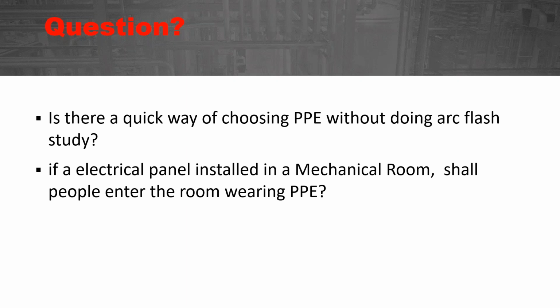Okay, thanks, Jay. Do you have any comments, Charlie? Yeah, absolutely, along those same lines. Here I want to promote Grace and what they call their safe test point, their voltage test station. I think this is a wonderful device, and I don't know if you see it in the background here, where I've got this device installed. The safe test point can go on industrial control panels. This would be a great reason to install one on older equipment, where company policy says it has to be de-energized. The safe test point connects to the incoming line voltage conductors coming in to the panel, and from the outside of the enclosure, without wearing PPE, you would test your tester.